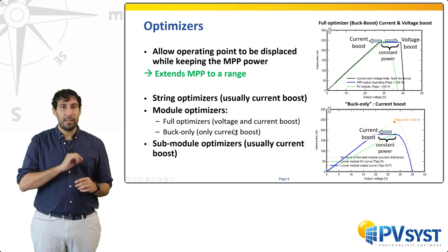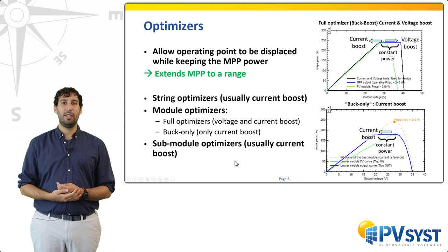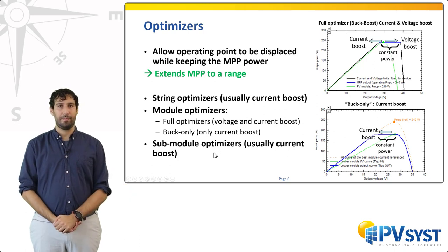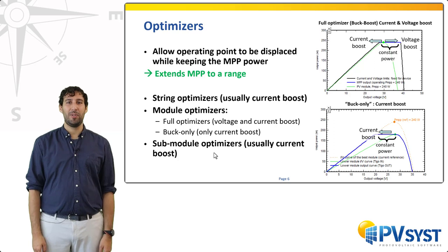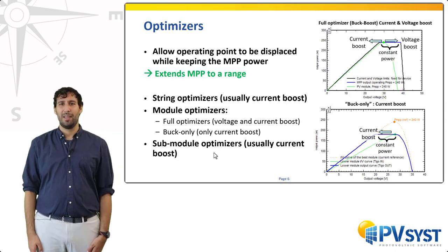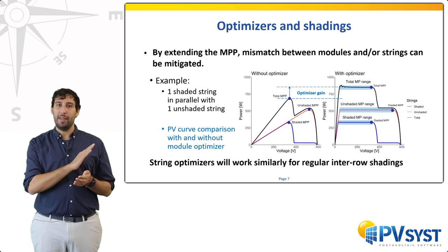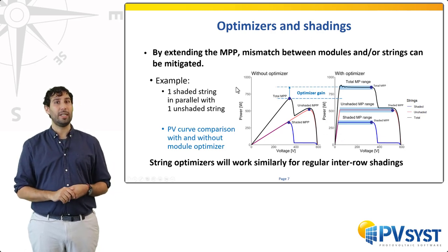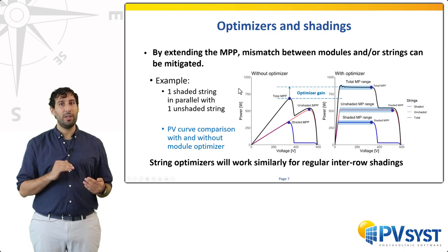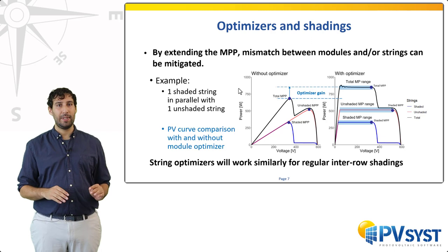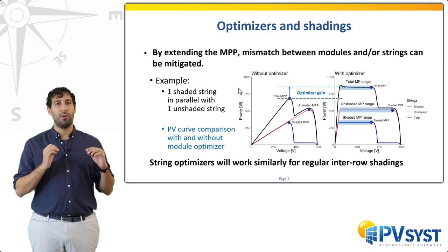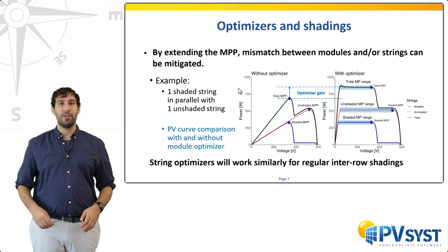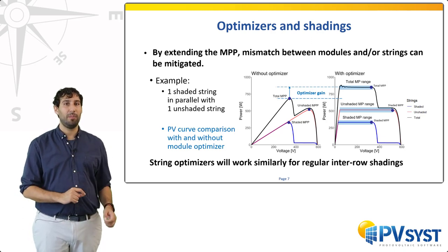Finally, sub-module optimizers are integrated in the module design. Natively, there will be three optimizers in parallel per module, and they lessen the necessity of using bypass diodes. It is easy to understand how optimizers improve production in the context of shadings. By extending the MPP to maximum power ranges, it is easier to find an operating point that fits all maximum powers of the individual components. In our earlier example of two strings in parallel, one shaded and one unshaded, one can see that using module optimizers, there is now a range of voltages that allows for the maximum power to be the sum of both individual maximum powers. You could reach the same results with string optimizers, and slightly better with sub-module optimizers.